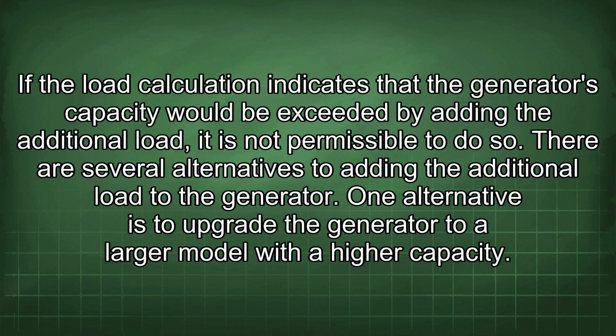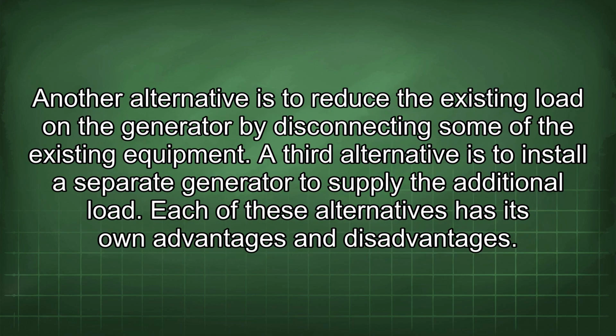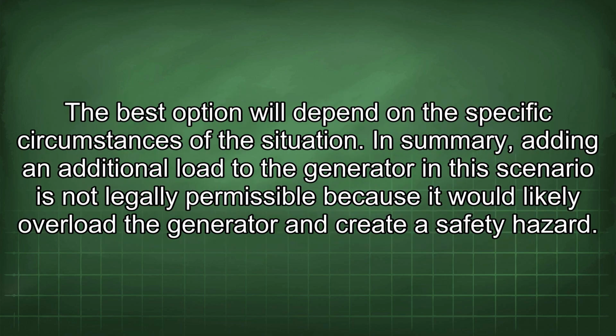There are several alternatives to adding the additional load to the generator. One alternative is to upgrade the generator to a larger model with a higher capacity. Another alternative is to reduce the existing load on the generator by disconnecting some of the existing equipment. A third alternative is to install a separate generator to supply the additional load. Each of these alternatives has its own advantages and disadvantages. The best option will depend on the specific circumstances of the situation.